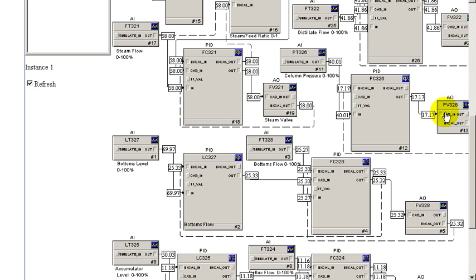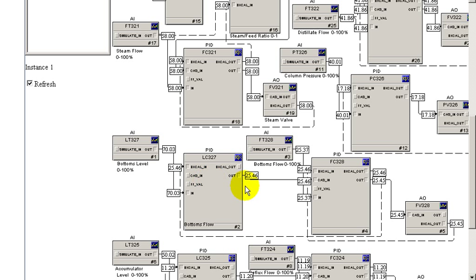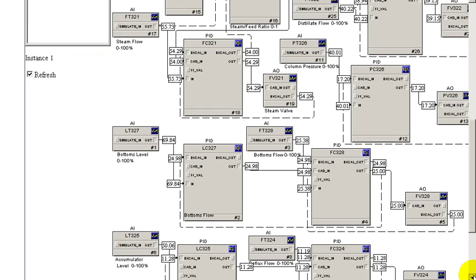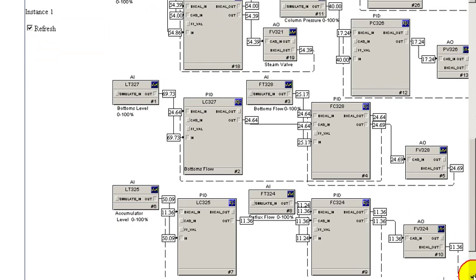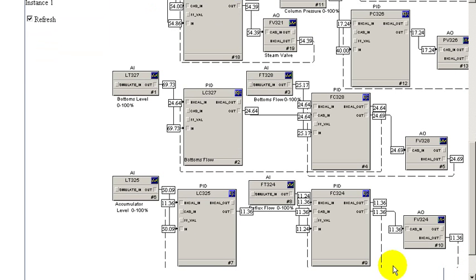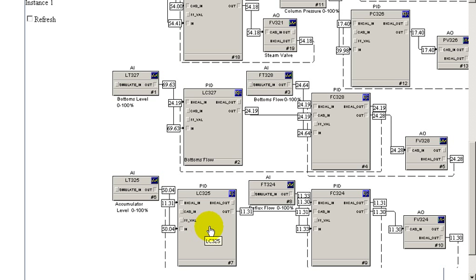The other control is shown here. The column pressure control is a single loop. The level control is adjusting the flow set point of the bottoms flow. And then the accumulator level control using a PID that's adjusting the reflux flow of our column.